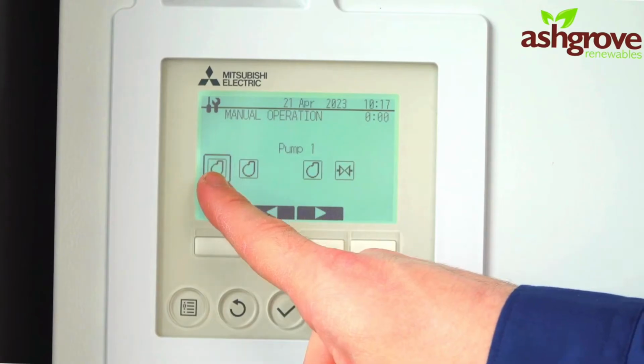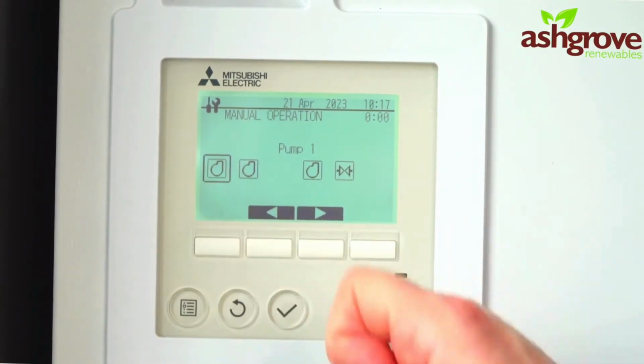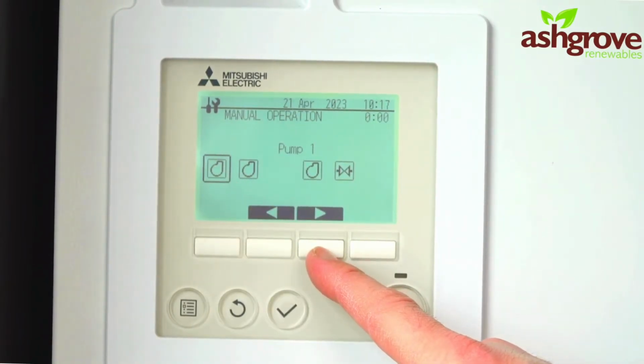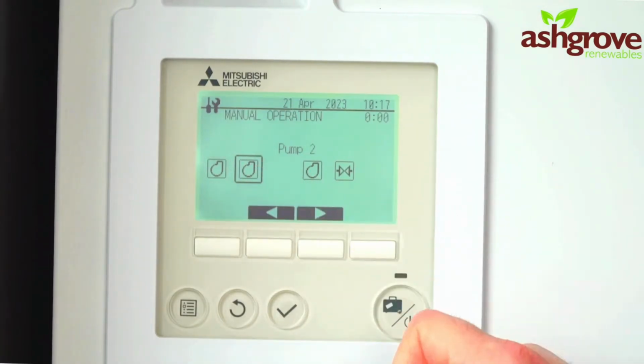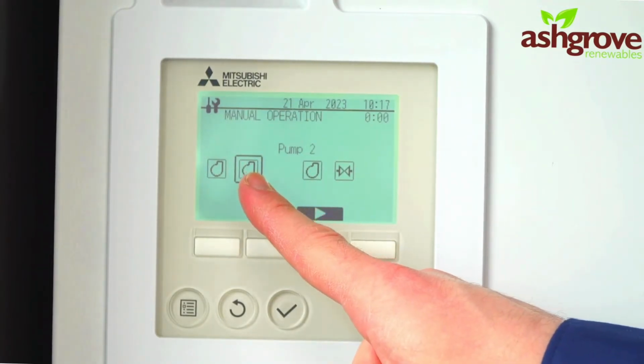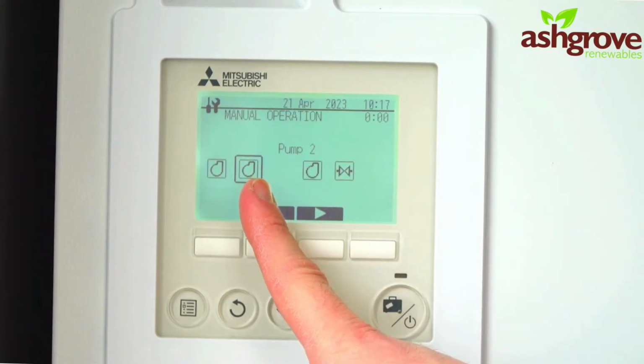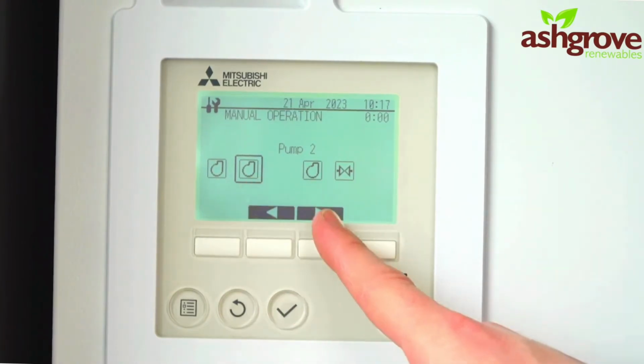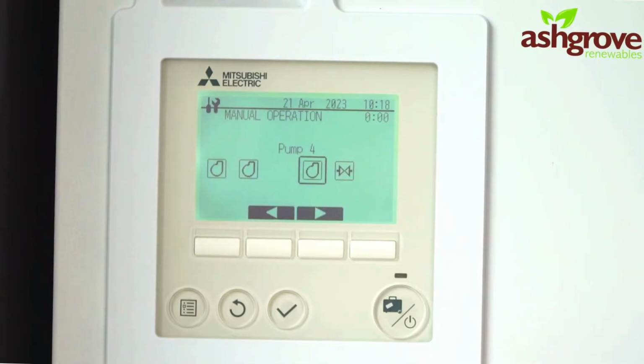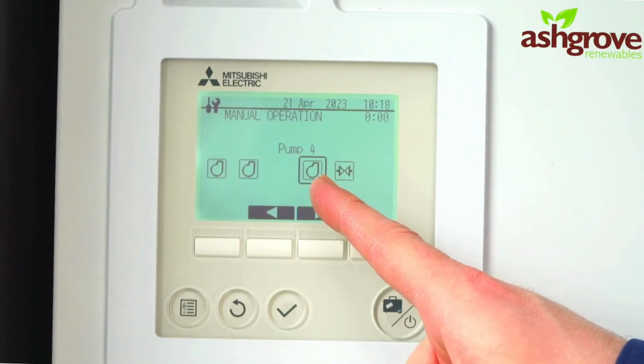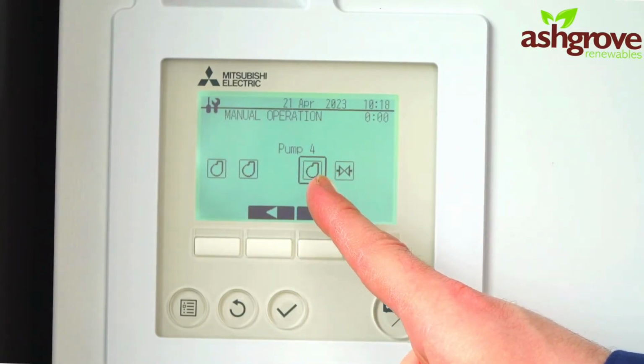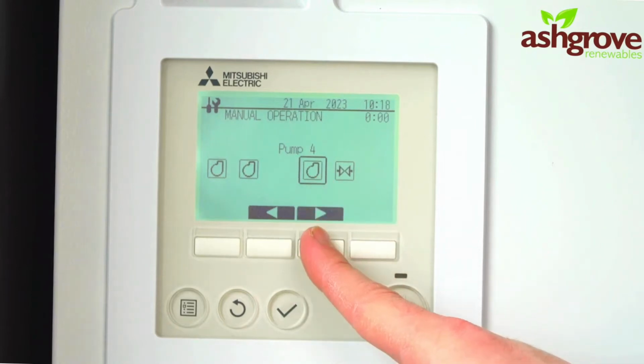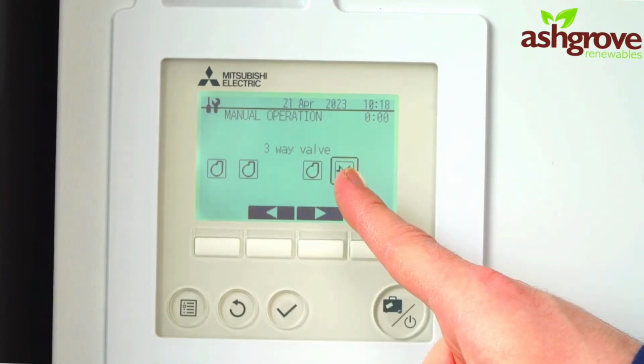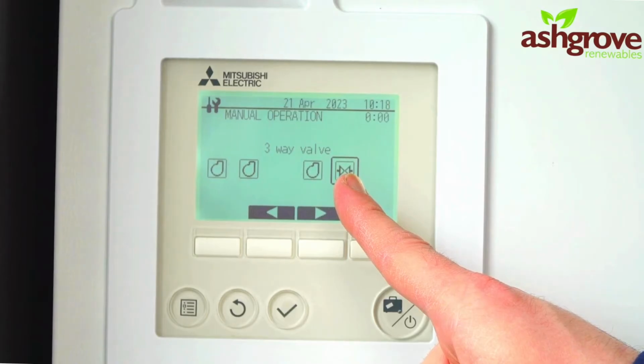Pump 1 stands for the primary pump, doing heating and hot water. Pump 2 is the heating pump, an extra pump because this is a big house. There's an extra pump on the line for heating only. Pump 4 is because there is a bronze pump circulating through a plate heat exchanger, as there's no coil in this Ecodan indoor unit. 3-way valve means the diverting valve between heating and hot water.